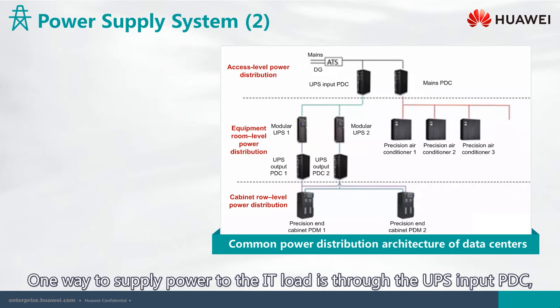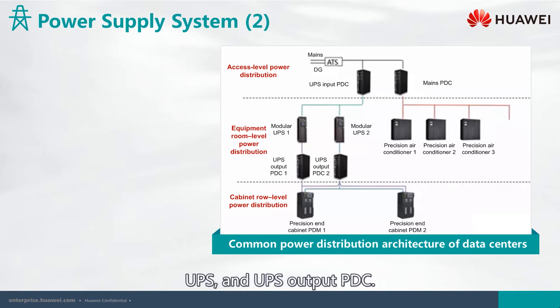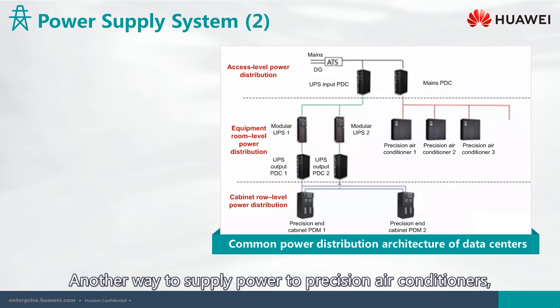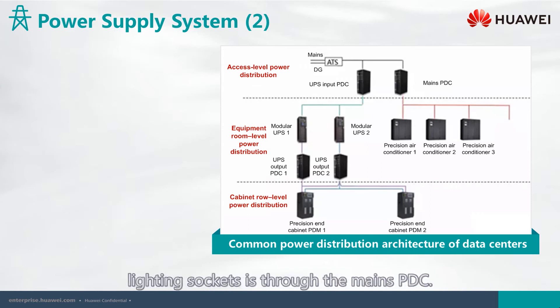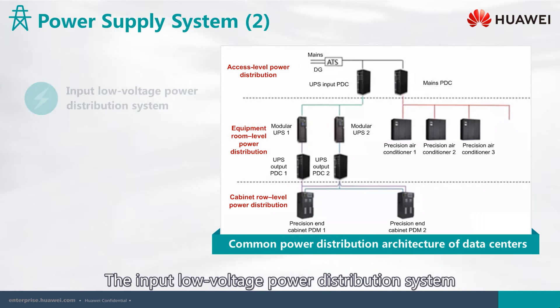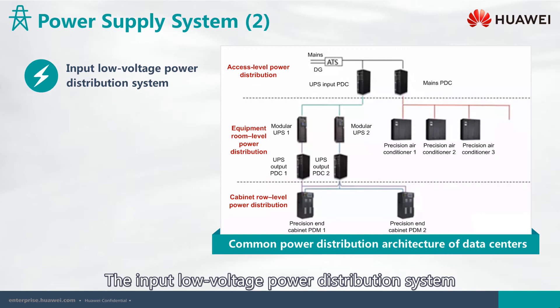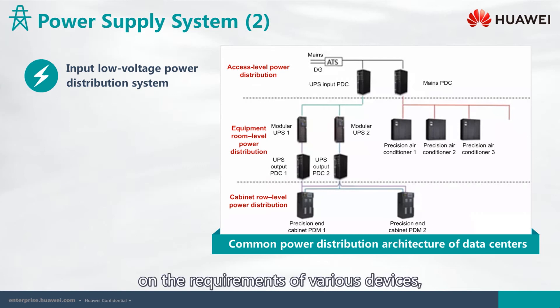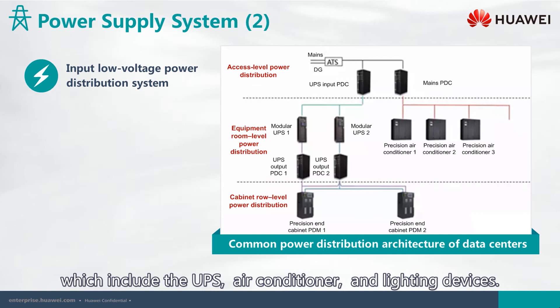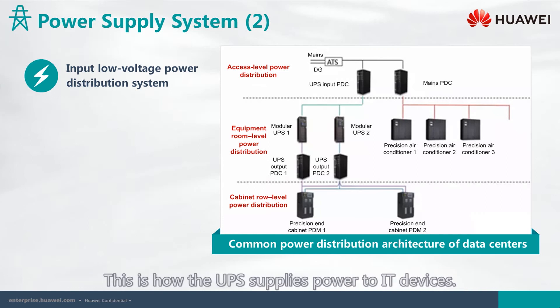One way to supply power to the IT load is through the UPS input PDC, UPS, and UPS output PDC. Another way to supply power to precision air conditioners, lighting, and sockets is through the mains PDC. The input low voltage power distribution system distributes the upstream power based on the requirements of various devices, including UPS, air conditioner, and lighting devices.